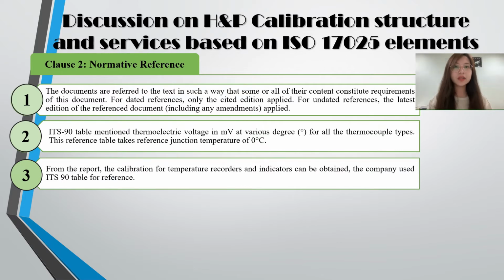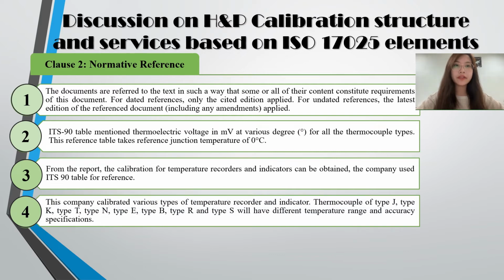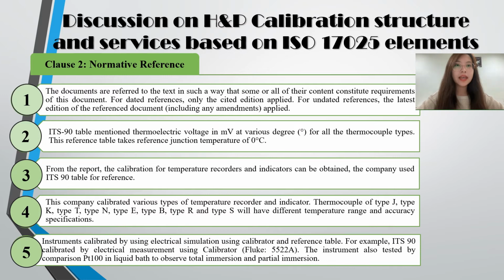Hence, the company used the ITS90 table for references. This company calibrated various types of temperature recorder and indicator. As stated here, different types of thermocouple will have different temperature range and accuracy specifications. Besides, calibrator and reference tables are used in the instrument calibration by using electrical simulation.